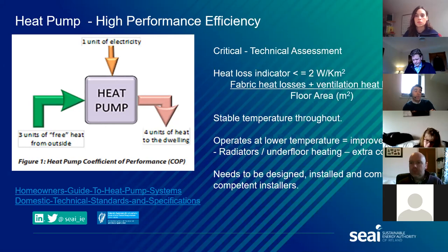And then ultimately, it's just reinforcing what Barry was saying in terms of the standards. So it needs to be installed by competent installers, and it needs to be commissioned, because I think we all know the stories where heat pump technology was installed and tests done with the Energy Savings Trust where they weren't meeting half the efficiencies they should have.